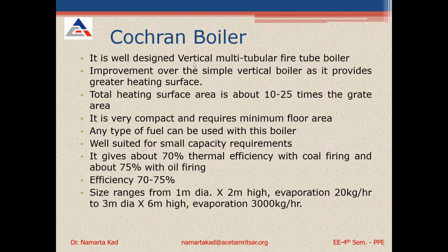It is a well-designed vertical multi-tubular fire tube boiler. It is an improvement over the simple vertical boiler as it provides a greater heating surface. Total heating surface area is about 10 to 25 times the grate area. So if the grate area is in the ratio of 1, it gives you 25 times the heating surface area. It is very compact and requires minimum floor area. Floor area is minimum, but its height is very much. The height is more, but the floor area is less.